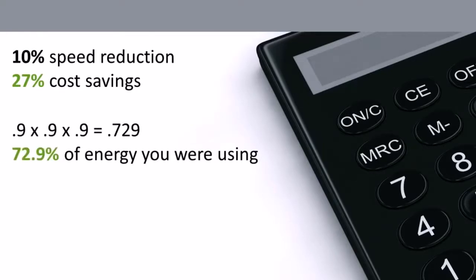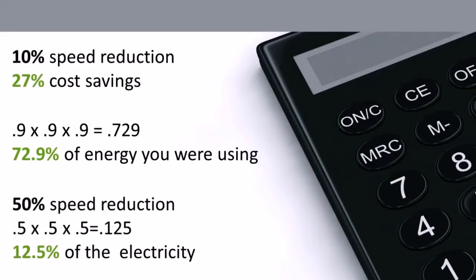Well, if you cube 90%, or 0.9, by multiplying 0.9 times 0.9 times 0.9, the net result of that is 0.729. So now you're only using 72.9% of the energy you were using. The difference between that and 100% is your savings. So with a 10% reduction in speed, you save 27%. If you're at half speed, or 30 Hertz, it's even more. Multiplying 0.5 times 0.5 times 0.5 is 0.125, so you're only using 12.5% of the electricity. Below this, you're really not going to get any more significant additional savings.